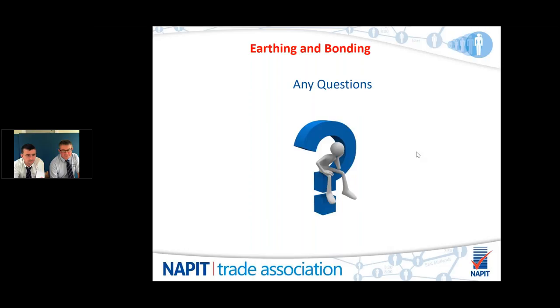Great, and I did say last question, but we've got one final one for you, I promise, because you've got 2 minutes left. So this is from Vernon. He's asking, does the main bonding cable have to be terminated at the MET, or can it also be terminated within the consumer unit? Yeah. Either. Doesn't matter. Usually take them back to the consumer unit because that's where all your cables are going anyway. But it doesn't have to. It can go to the main earthing terminal in the outside cabin, or the main earthing terminal on the meter board, whatever.